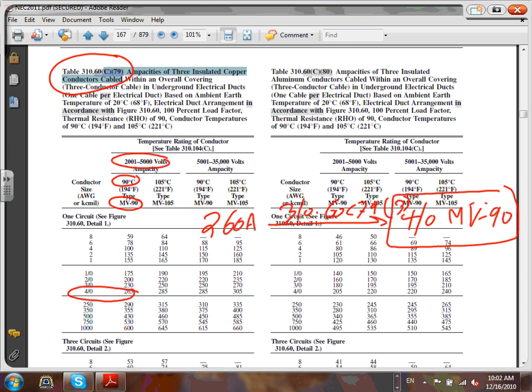You said 3 aught, but it's a 4 aught. Oh, 310. Okay, yeah. Why did you decide to go off that one when there are 3 different cables? Very good point. Read the top. You can choose anything; it becomes based on the installation. How are you going to be installing your systems? I really don't want to go there, but see where it says detail 1? The most common one is called detail 1. If you go back a couple of pages in your code book, you're going to find detail 1.